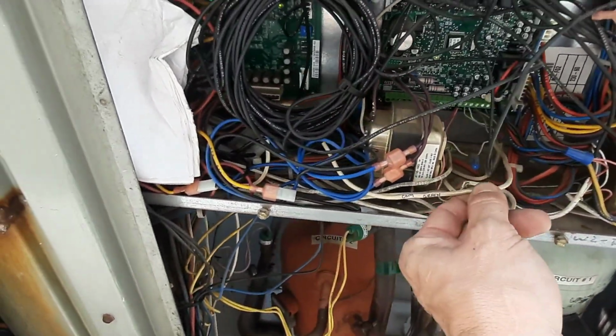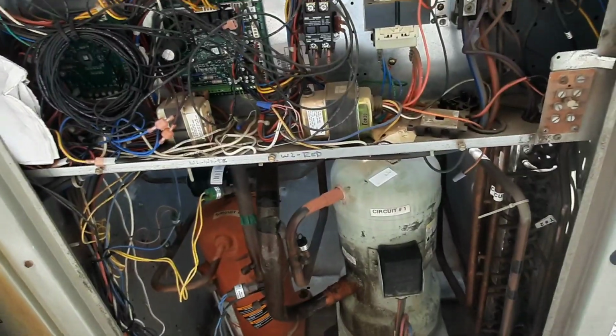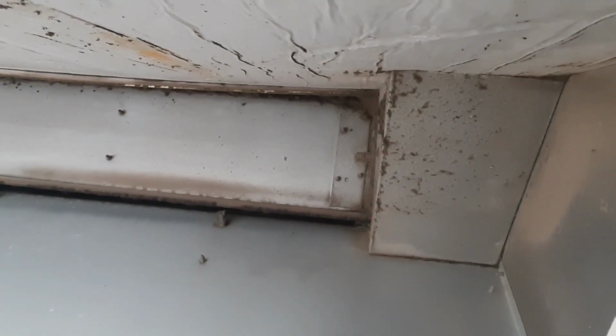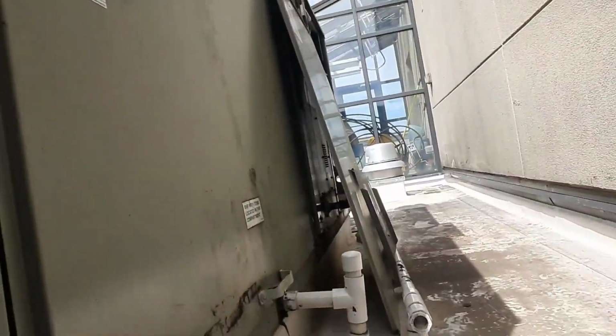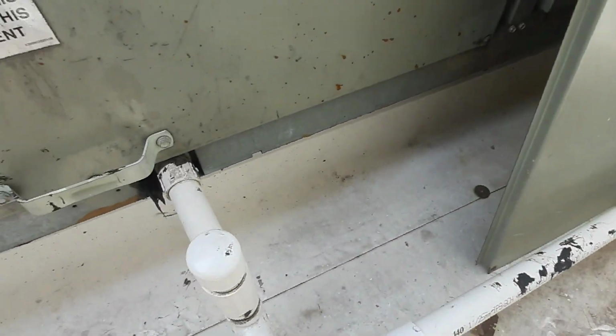There's our COM here. COM green. Interesting. So we're going to watch it for a little bit. Hopefully my maintenance guy shows up and tells me something that I don't know. Oh, look, we're filtering our outdoor air really well. The economizer's not open. Barometric relief is dirty and just falling apart. Lord only knows where that filter went, but I shouldn't have a problem with the economizer, because that could have been with these cool mornings we've had. We get 50 and 60 degree mornings. Economizers will throw you off sometimes.